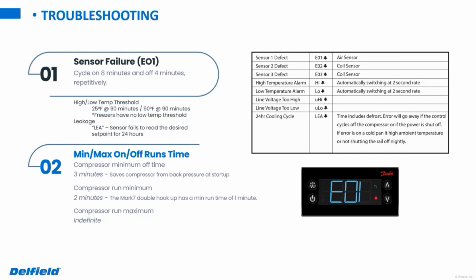So on a cooler, you may be able to get away with that for a few days without having issues with freeze-ups. On a freezer, it's probably a little bit more urgent to get that probe replaced, but just something to keep in mind if you happen to see that E01. The unit should continue to cycle the condensing unit for that 8 minutes on, 4 minutes off, but I would definitely recommend getting that one replaced as quickly as possible.